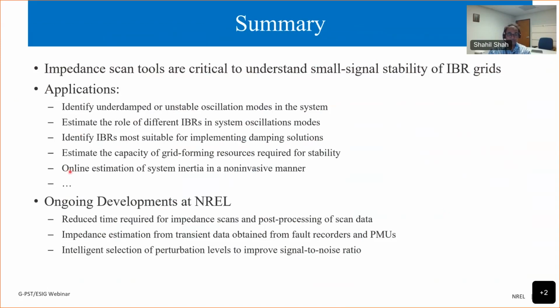The last part, one application that I did not talk about, is online estimation of system inertia in a non-invasive manner, which is what we have done at NREL for a real 2 megawatt synchronous generator. And in terms of the ongoing developments, we are trying to reduce the time it takes for impedance scan and post-processing of scan data, developing methods to estimate impedance from just real measurements from fault recorders and PMU, so that in future, I think we are getting a lot of data.